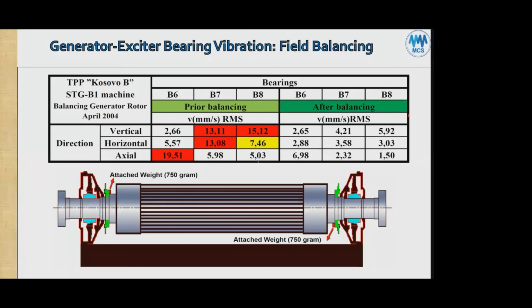Now, the magnetic unbalance will be load related, but it is going to have a much shorter time transient than thermal. If it's thermal heating on this rotor or thermal heating in the stator, for example, if there's a problem in the stator, it can also cause trouble for the rotor. It causes unusual vibration. For example, if you have a stator here and a high temperature right there due to an insulation problem, it will heat the rotor where? Notice it's not touching the rotor, correct? But it will induce heating of the rotor from radiation and convection, even though there's no contact, and therefore it will heat it up here. And what happens? It's going to start to have a thermal bow. Even though this is rotating and it's going to be almost equal temperature circumferentially, it's going to be unequal in the axial direction. Like here it might be, who knows, 100 degrees Celsius or less, and here it might be 150 Celsius.